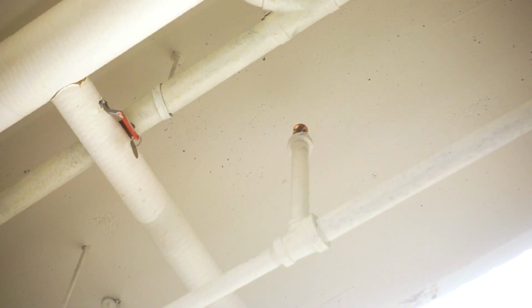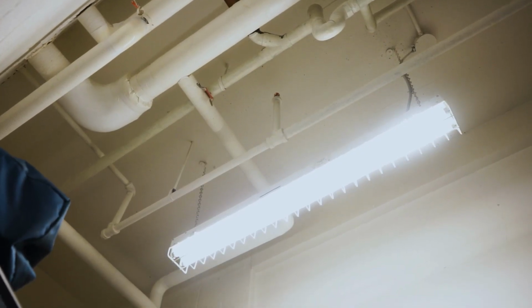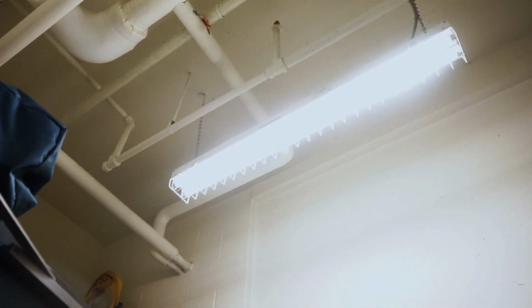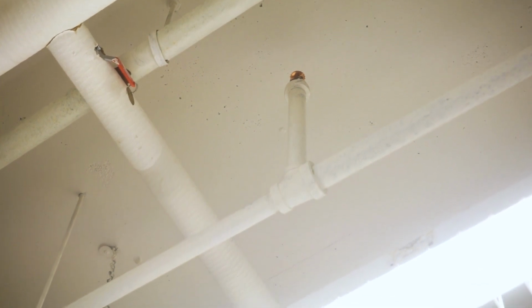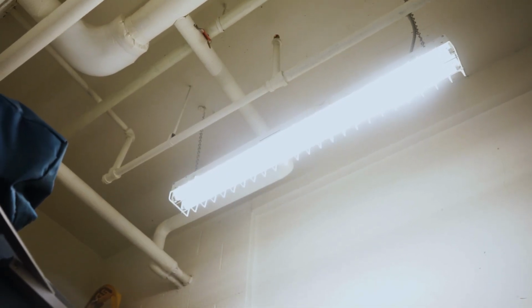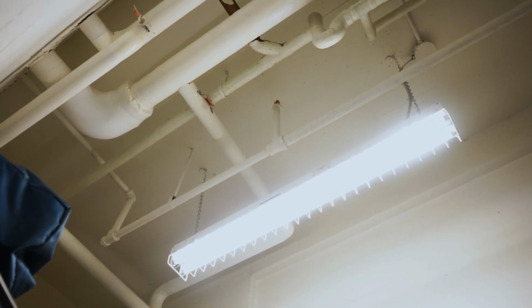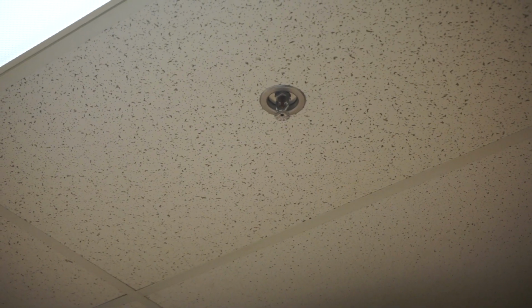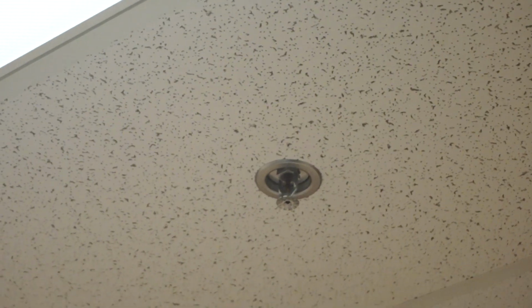So there are 3 different types of sprinkler heads because there are 3 different types of applications in this building. So here's one application, folks, of what a sprinkler head looks like. If fire were to occur right now underneath that sprinkler head, the heat would rise. As the temperature of the fire would increase, it would get to the sprinkler head, activate the sprinkler head, and then water would come out of that pipe and rain down on the fire below it. So here's another example of a sprinkler head at the elementary school, and this sprinkler head serves the exact same purpose. When a sprinkler head goes off, the entire system does not operate. Just the affected sprinkler head will go off. It's not like we see in a movie where a sprinkler head goes off and then the entire floor space, each one of the heads activate. It only activates for the area where the fire is located.